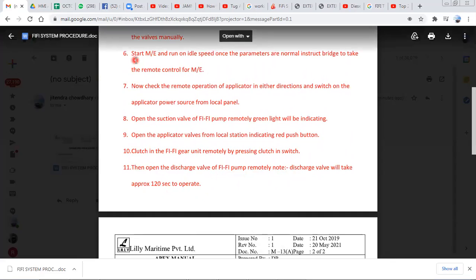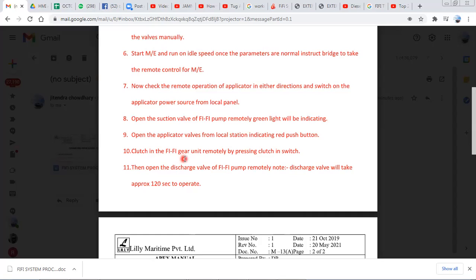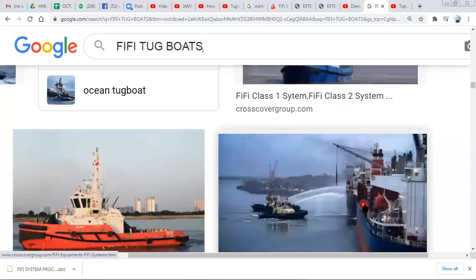So the main thing is: start the main engine, set everything, give control to the bridge, test the applicator, then clutch in the firefighting pump and open the discharge valve. This gets water into the FIFI foam monitor, and like this, tugs can fight fire in case of fire on any ship, platform, or anywhere.